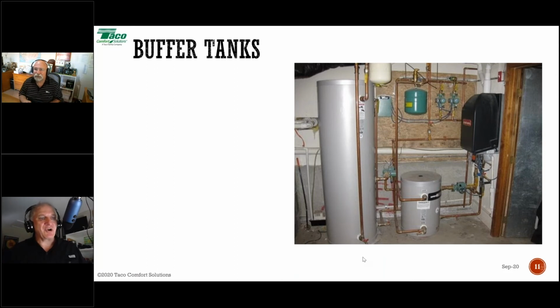That's going to happen regardless, whether you have a delta T pump, whether you have a delta P pump, or whether you have a fixed speed pump as your system pump, as your delivery heating pump. That's going to happen anyway. It's not going to happen any more with a delta T pump than with a delta P pump because we have a minimum speed on a delta T pump anyway. Right. So when you hear something like that, it's coming from someone who doesn't really quite understand how these things interact, or system design or system operation. So don't get too flustered about that part of the equation.